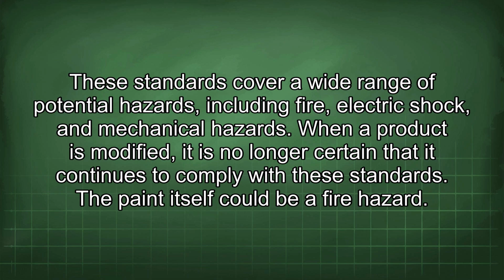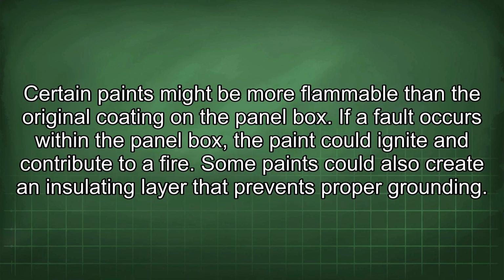When a product is modified, it is no longer certain that it continues to comply with these standards. The paint itself could be a fire hazard. Certain paints might be more flammable than the original coating on the panel box. If a fault occurs within the panel box, the paint could ignite and contribute to a fire. Some paints could also create an insulating layer that prevents proper grounding.